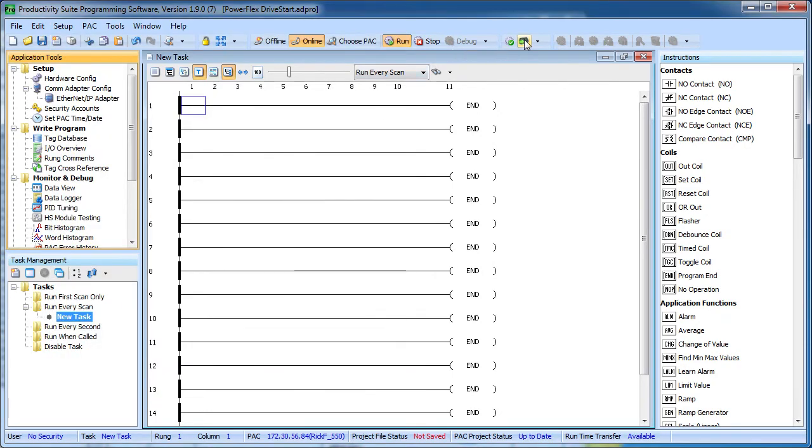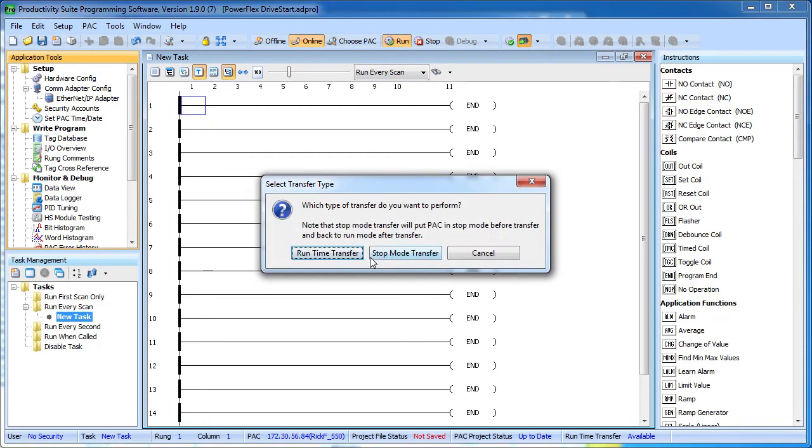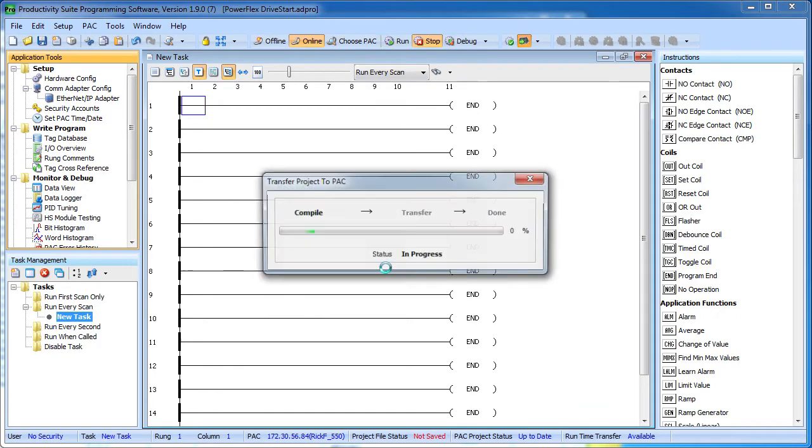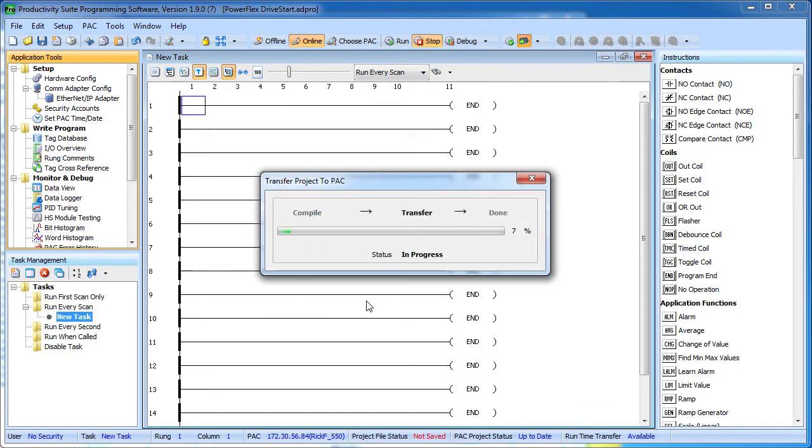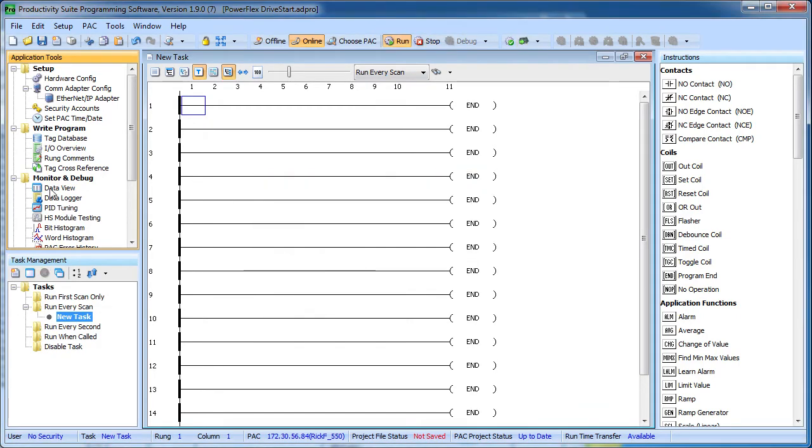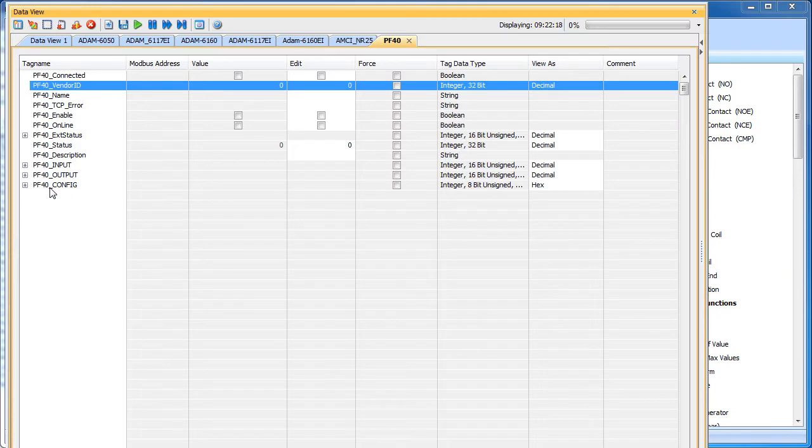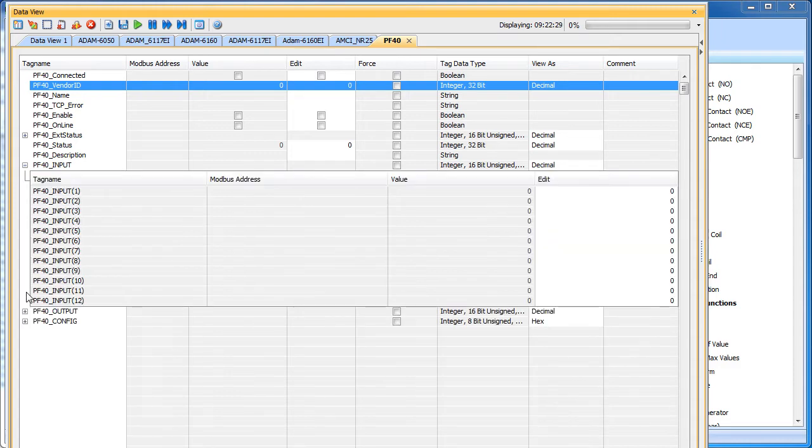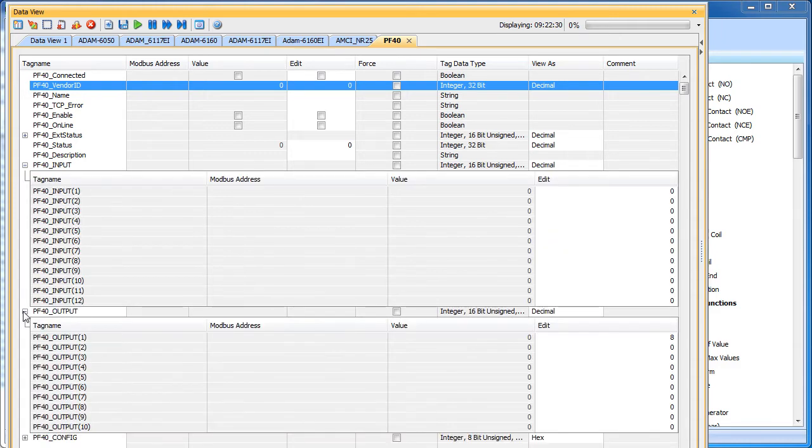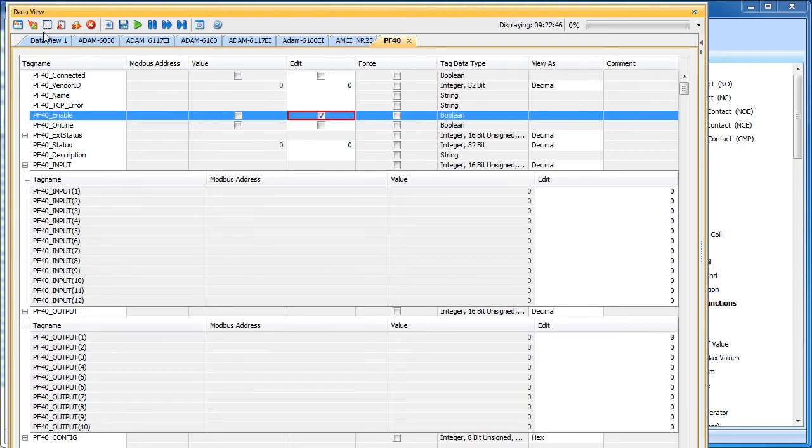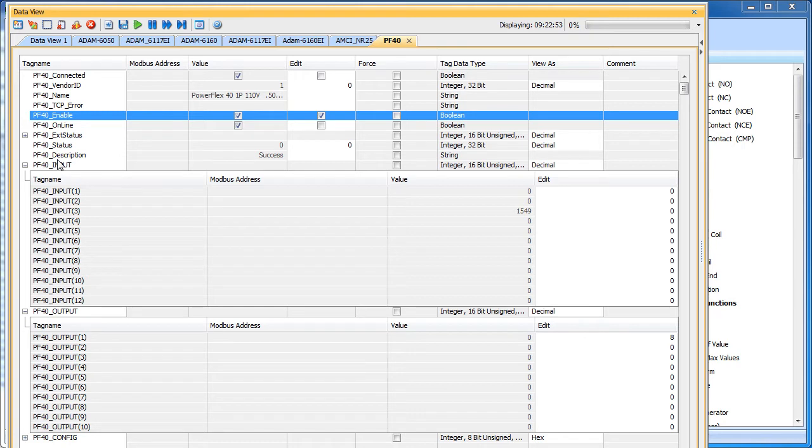OK, well let's give it a try. Let's transfer the program down to the Productivity 3000 and bring up our data view that we created. Here's that PF40 tab on the data view that was created for us by that monitor button. I'm going to expand the input and the output arrays and now all we need to do to enable communications with the drive is flip this enable bit right here. So I click on him, write that out and sure enough we're connected, we're online and we have a successful connection.